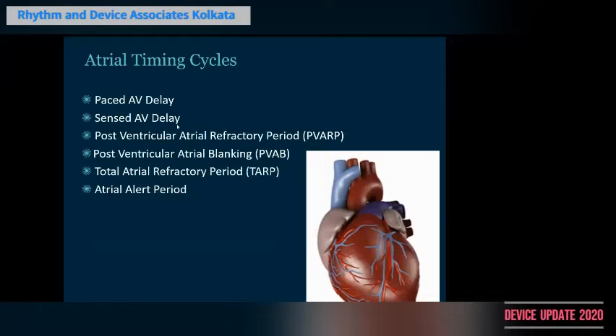So, atrial timing cycle review. Here you have a sensed AV delay. If you can see, the pink marker starts from the onset of the P wave and ends into the Q wave. So this is a sensed atrioventricular delay. Suppose this sensed atrioventricular delay is 220 milliseconds. It will mean that after the onset of the P wave, at the end of 220 milliseconds, the ventricle will give a spike of pacing, which will then capture the ventricular myocardium. So this is what is sensed AV delay.